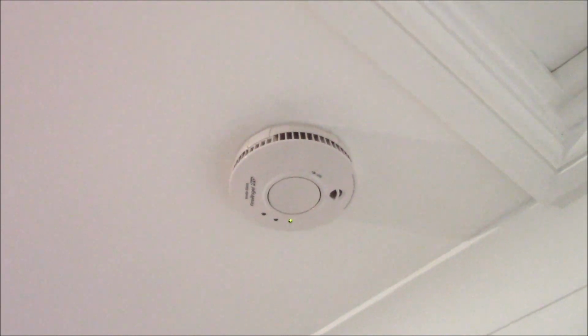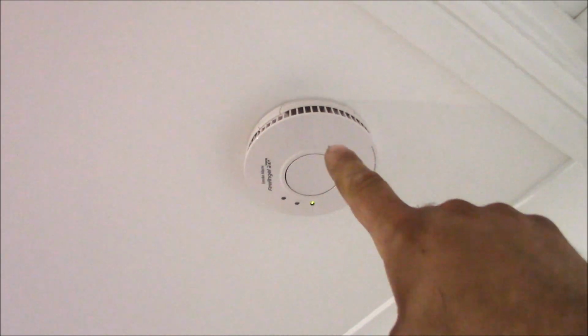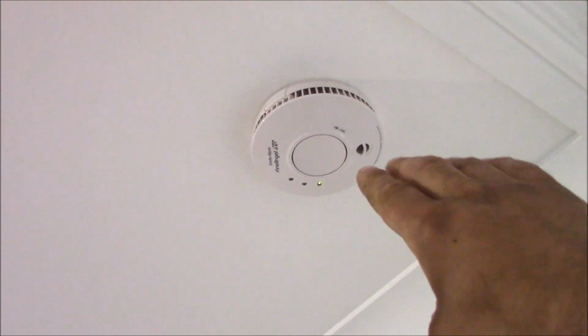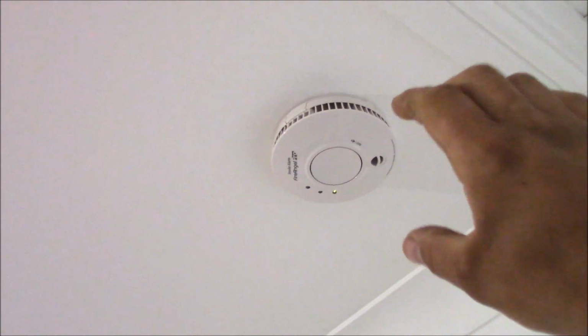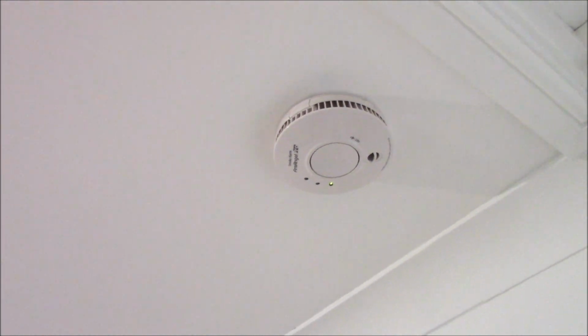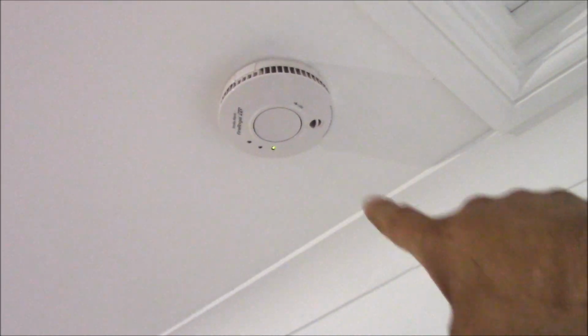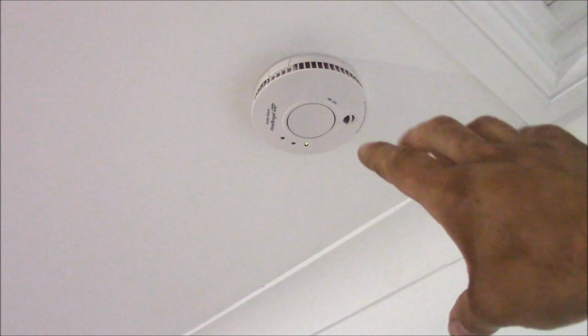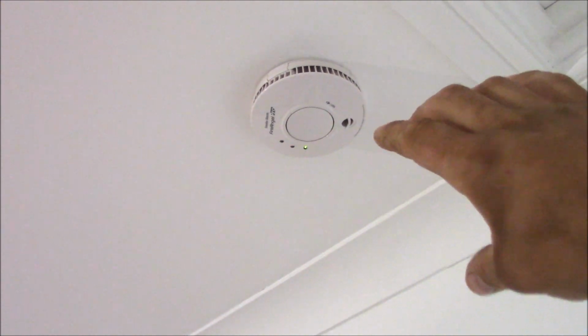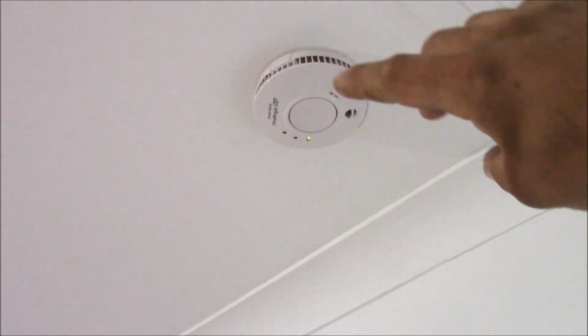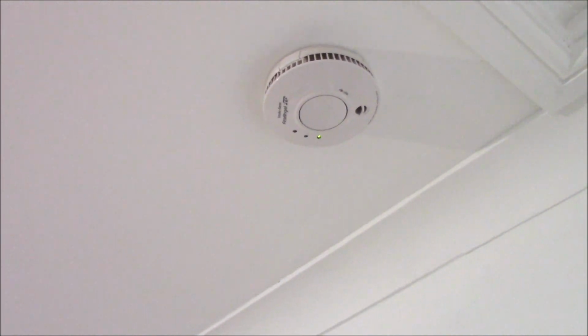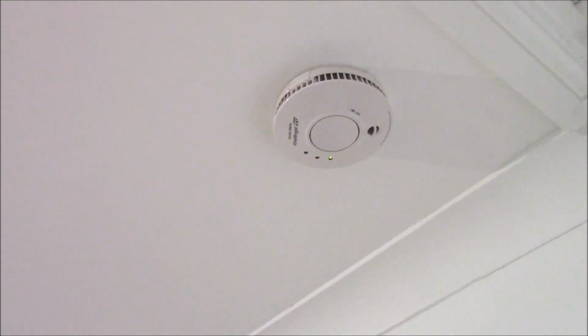Just when you install the smoke alarms, you need to remember that this should be on every floor, usually in a corridor, somewhere in the middle of the ceiling. The distance from the wall to the smoke alarm should be not less than 30 centimeters, and the same from the nearest light to the smoke alarm. In the kitchen you usually install the heat alarms.